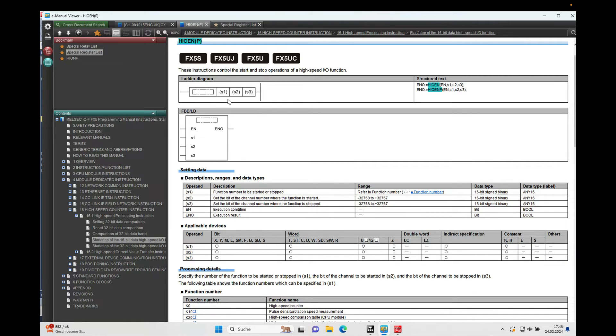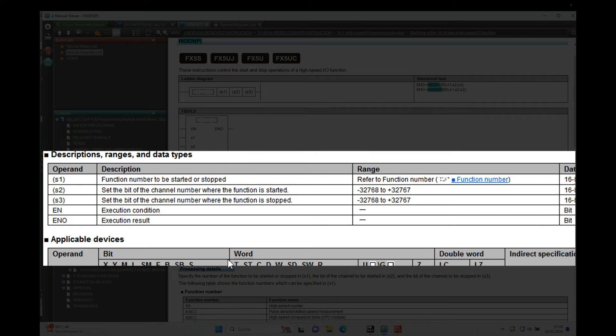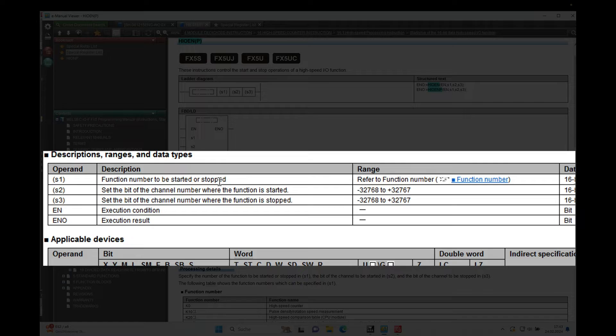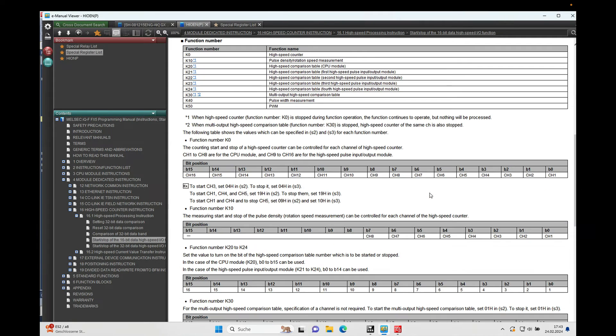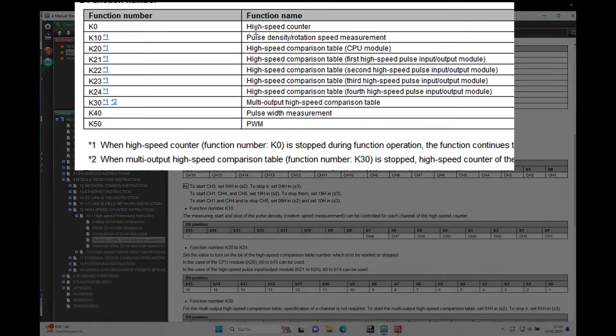So here we see the instruction itself, S1, S2, S3. And there is an explanation that says S1 function number to be started or stopped. And as we can see, if we push this link right here, we have a function number that says K0 for the high speed counter and K10 for the pulse density rotation speed.